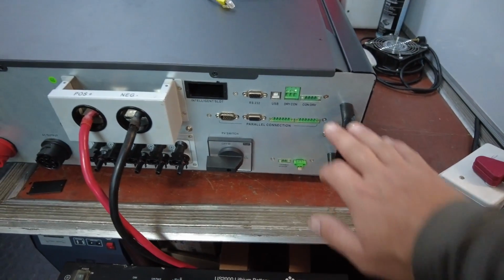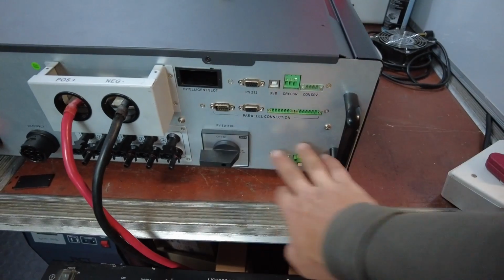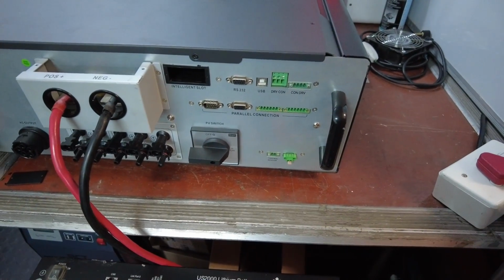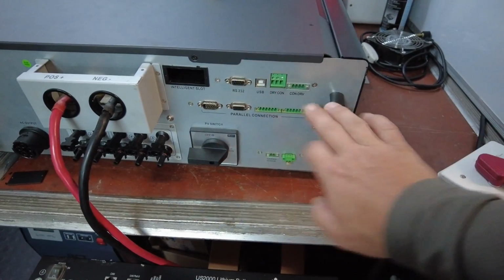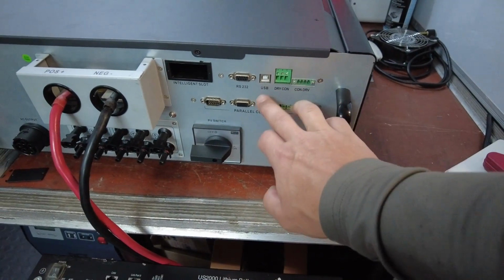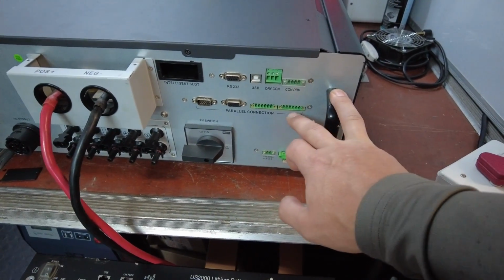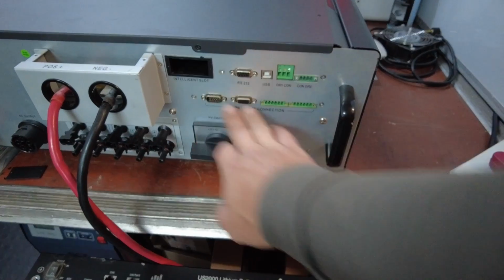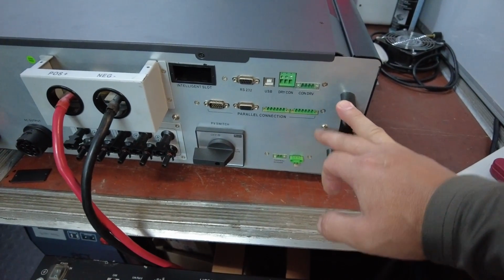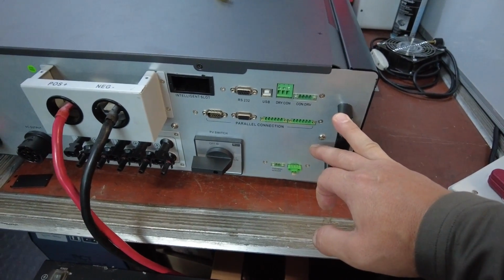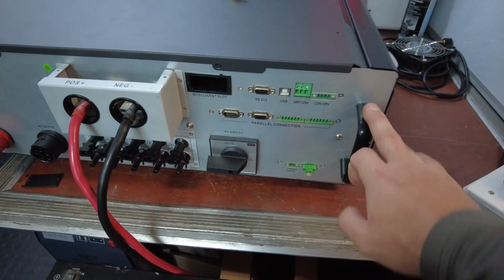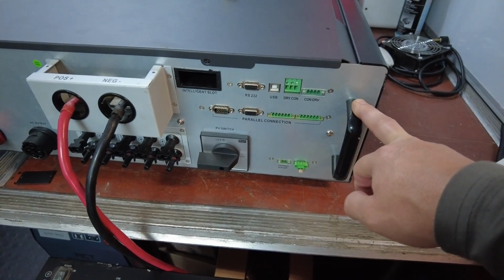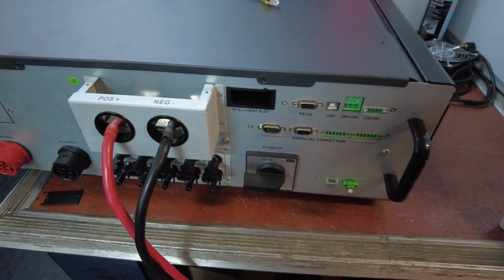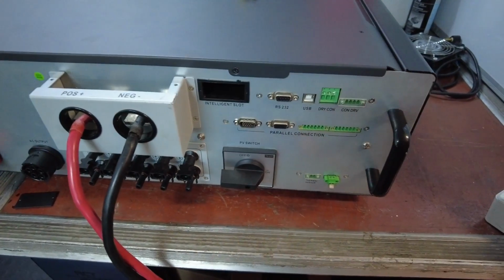If you come to the bottom of the inverter, you will find all of the communications ports. You have your RS-232, which is for your PC, as well as your USB, your dry contacts, and then your parallel connection when you connect more than one inverter. There is no BMS port on this. However, you do have this intelligent slot.